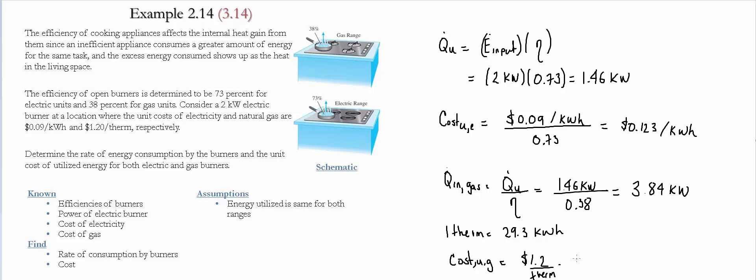We also divide it by the efficiency, in this case it's 0.38, and then we're going to do the conversion that one therm is equal to 29.3 kWh. So this gives us approximately $0.11 per kilowatt-hour.